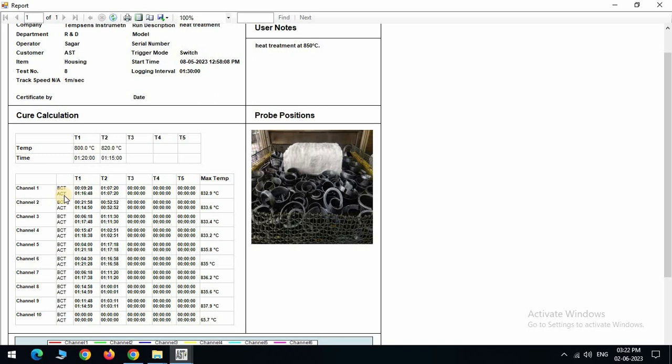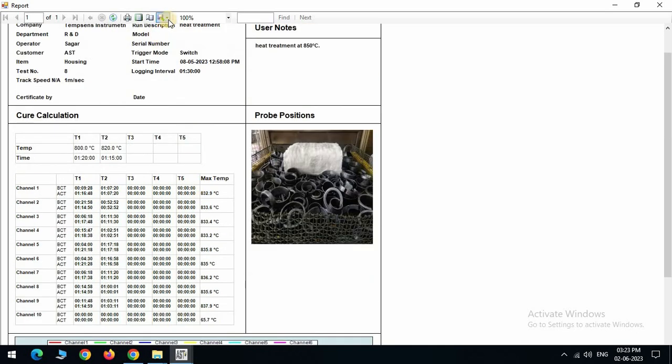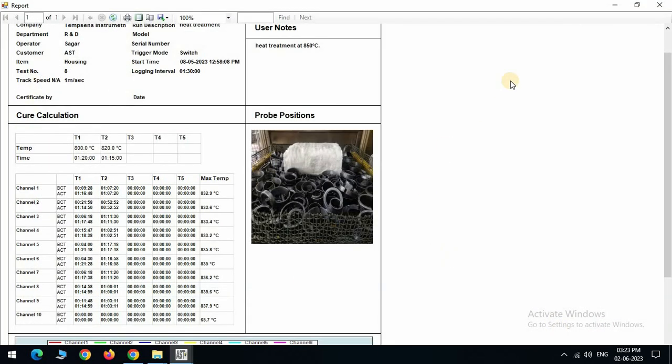ACT is actual curing time. The actual curing time is the duration required for the product to cure at a specified temperature above the set point. We can see the max temperature recorded into each channel. Now export the data via PDF mode and save it to the desired location.